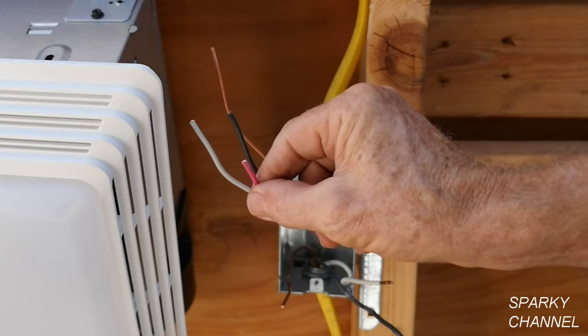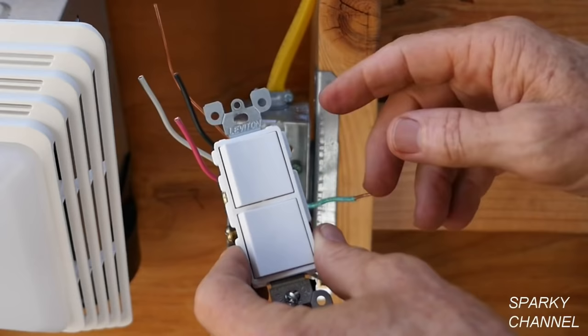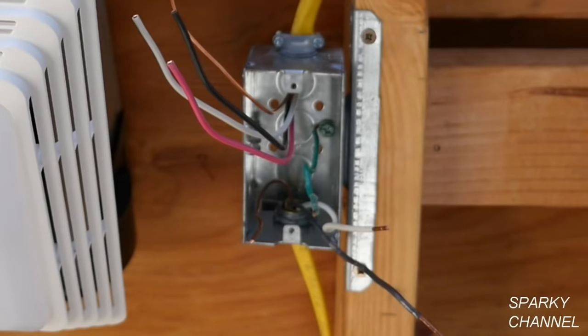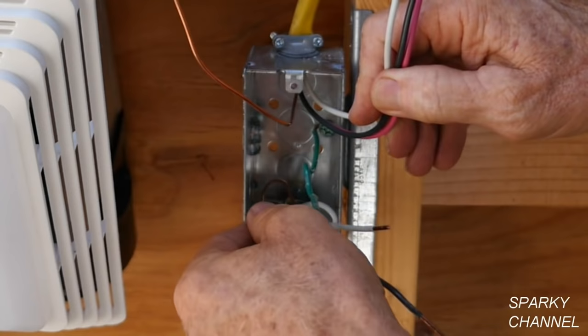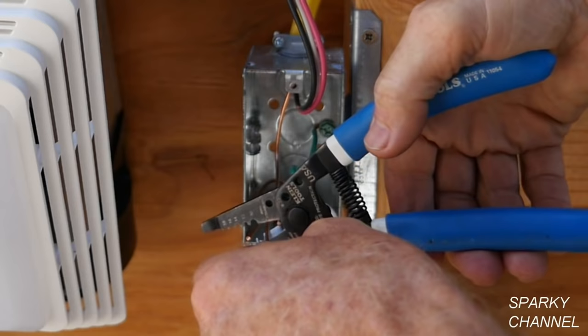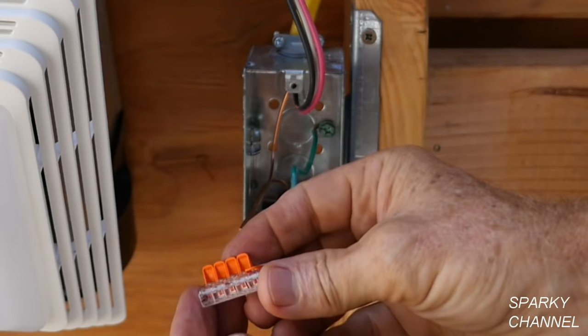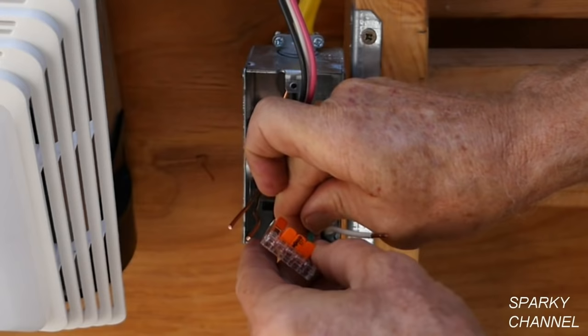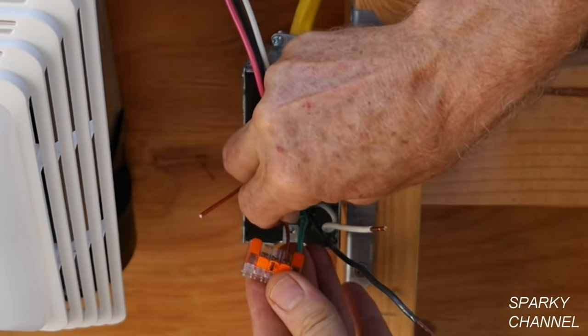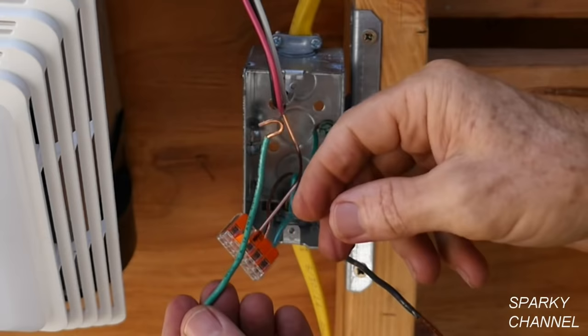Now I'm going to be using a Leviton double switch. I'm going to put the light on the top switch and the fan on the bottom switch. First, I'm going to take care of my grounds. We have a ground from the power wire coming in, a ground that bonds the metal box to the grounding system of the house, and a ground from the 12-3 with ground cable we just brought in. I'll cut them approximately even and use a five-connector Wago lever nut, putting a ground in each position and closing it down. Here's a grounding pigtail that will go to the switch itself — put that in and close it down. We'll put the grounds back in the back of the box.